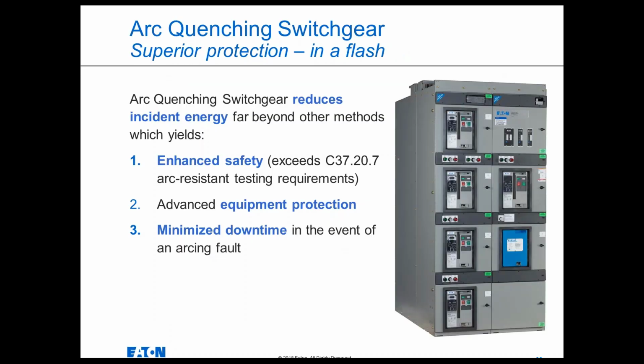So, in conclusion, arc quenching switchgear really just does one thing, and that is it reduces incident energy. But it does it to an extremely low level. And it's able to reduce incident energy to far lower than virtually anything else out there. And that's where all the other benefits come from. But it's really just an incident energy reducing technology that enhances safety and enables standard switchgear to exceed that arc resistant test requirement even when doors are open. It provides advanced equipment protection when there's an arc flash. And as a result of not having to do many or any repairs to the equipment after an arc flash, it dramatically reduces the downtime so that you can have your critical processes back up and running very quickly.